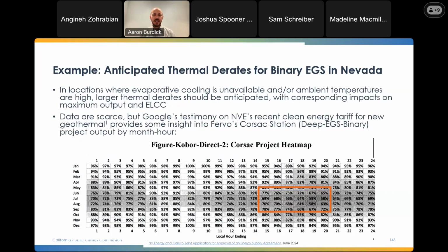One key challenge we've run into is that there isn't a lot of data for new geothermal candidate resource locations as to what level of ambient derates they would face. We found an example from testimony by NV Energy for their application for a new geothermal project in the Southwest, showing quite a high derate in output during summer, particularly in the late afternoon to early evening hours, up to a 30 to 40% reduction during those high temperature periods.